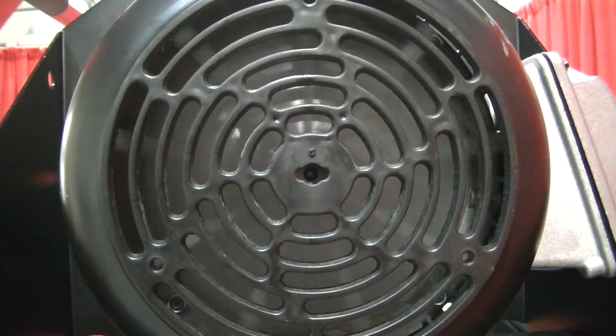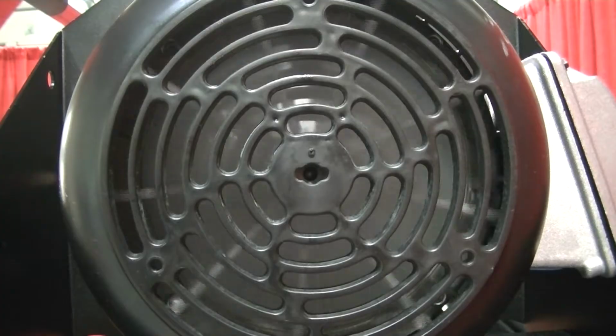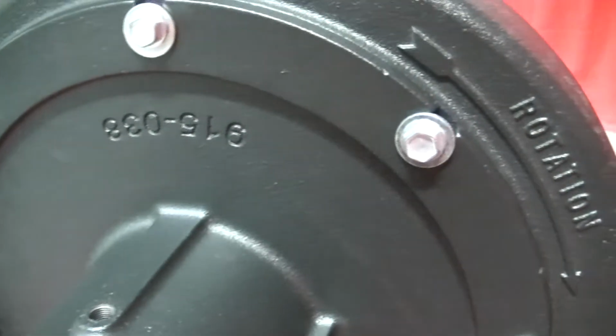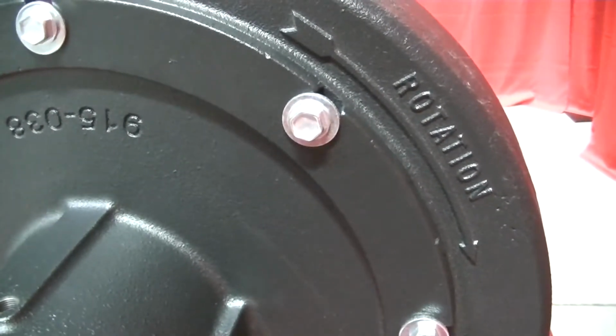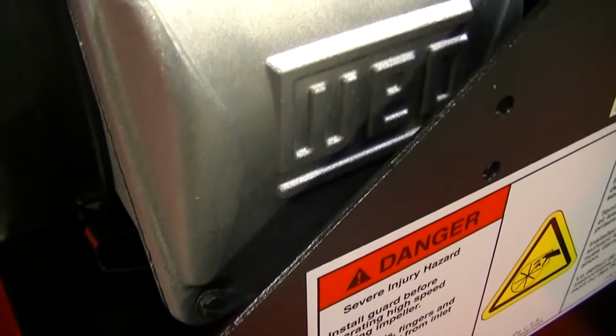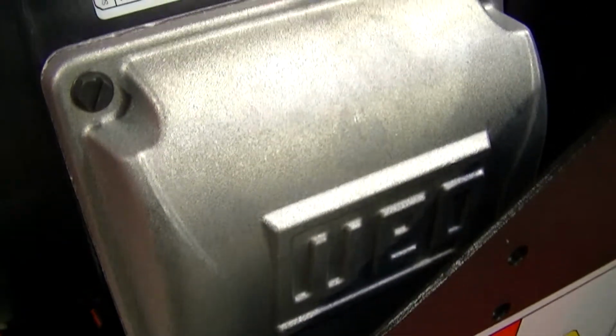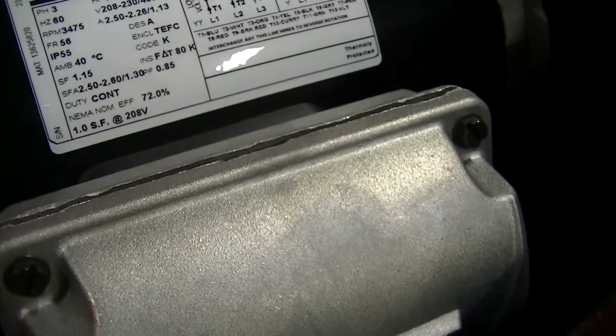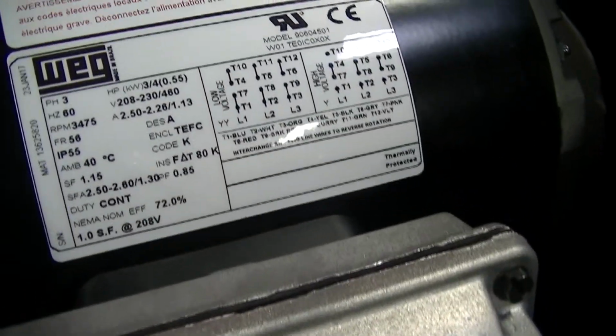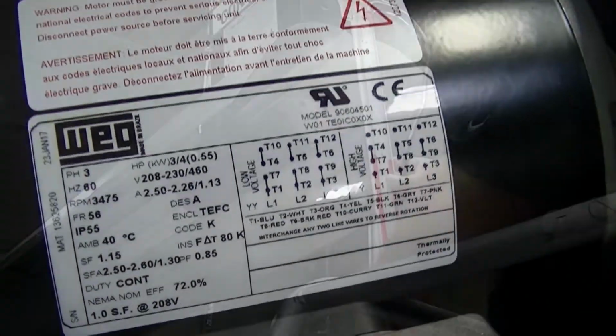Then, determine the direction of the rotation, making sure the motor rotation is turning in the direction of the arrow on the side of the pump. If the rotation of the motor is not in the direction of the arrow on the side of the pump, follow the manufacturer's instructions on the rating plate for reverse rotation.